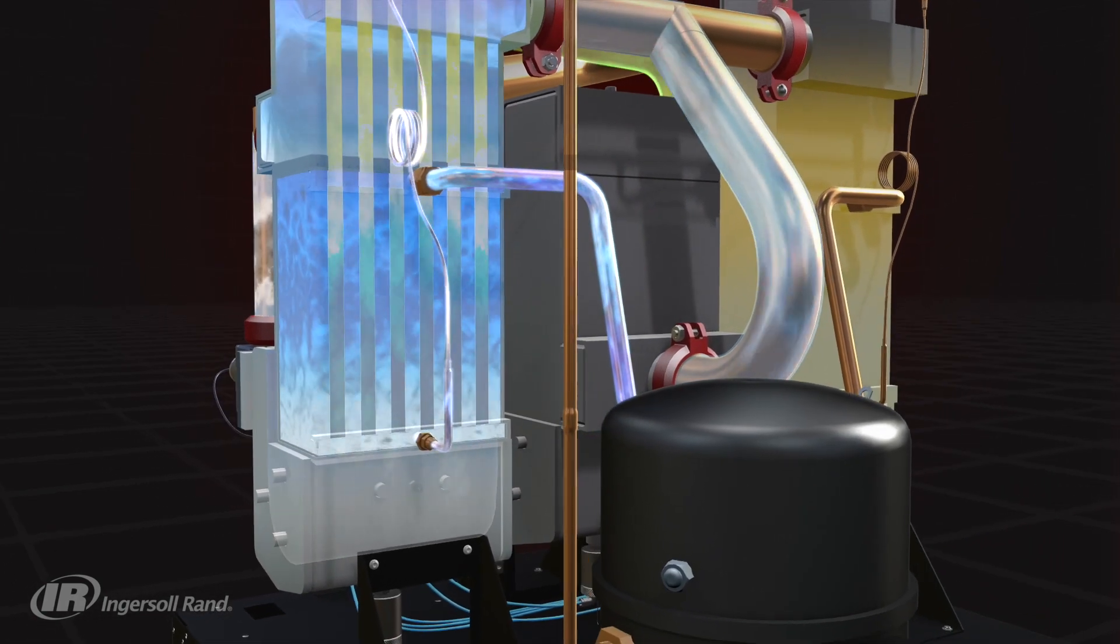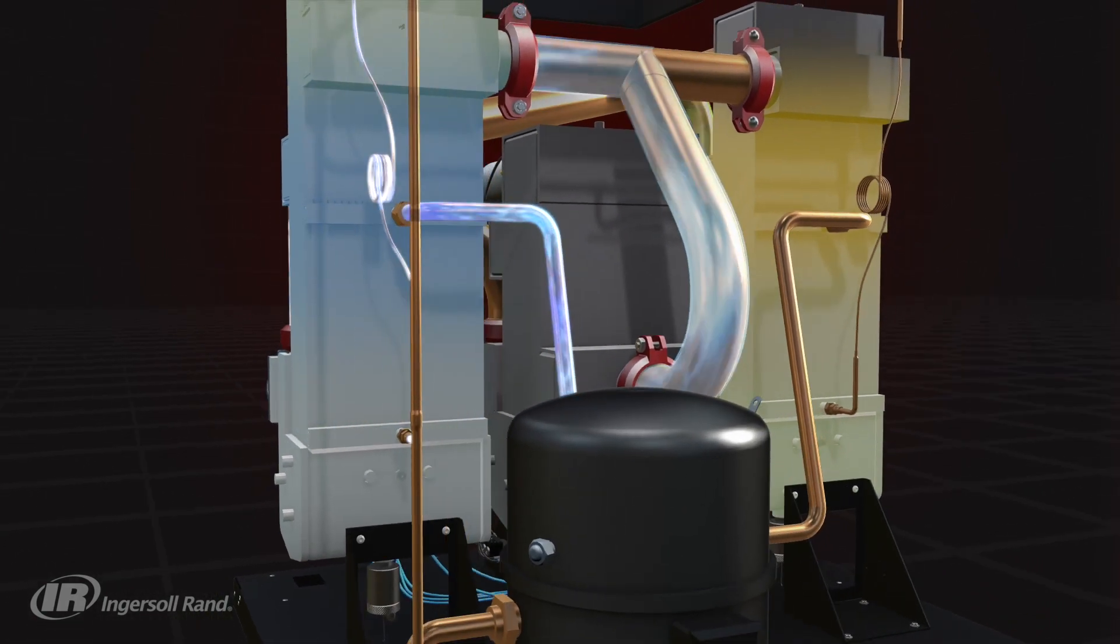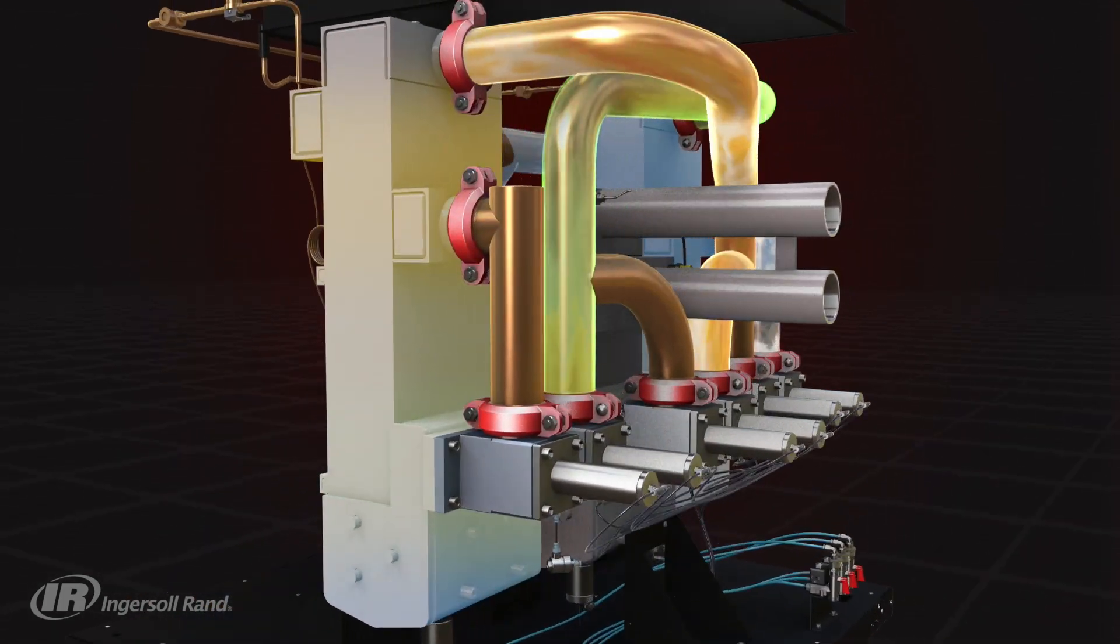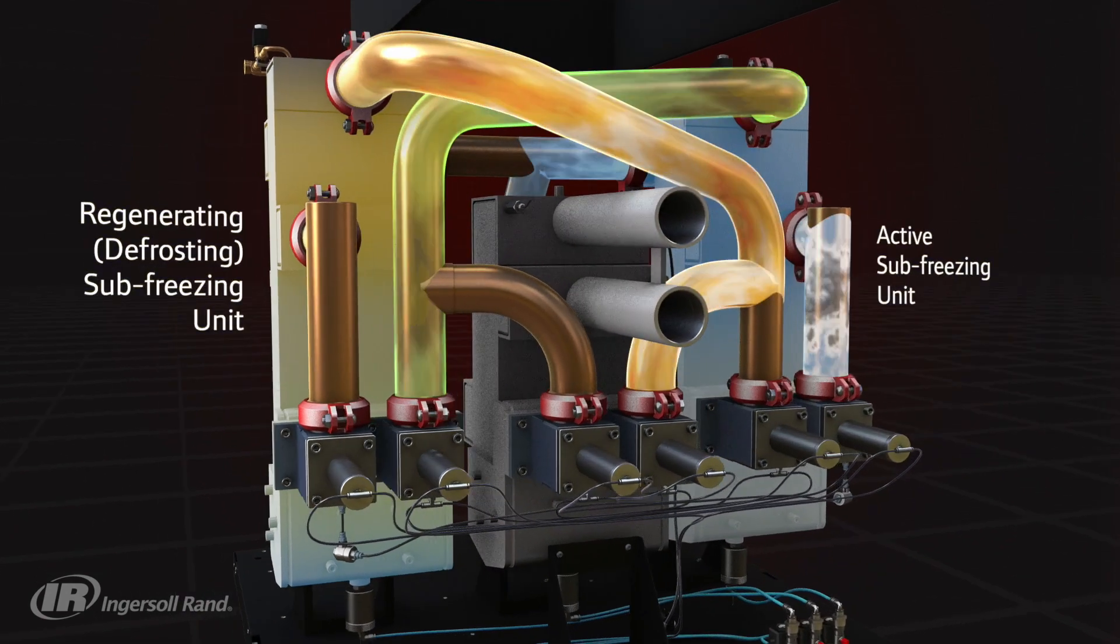Over time, frost accumulates on the internal surfaces of the active unit, and when the temperature of the non-active unit indicates it has fully defrosted, a switchover is triggered between the two units.